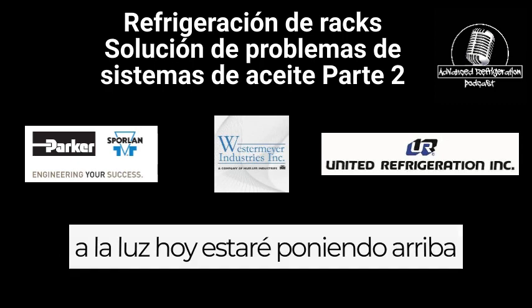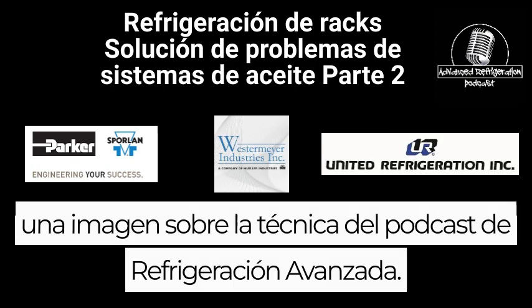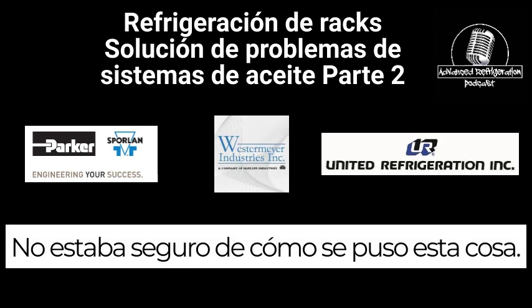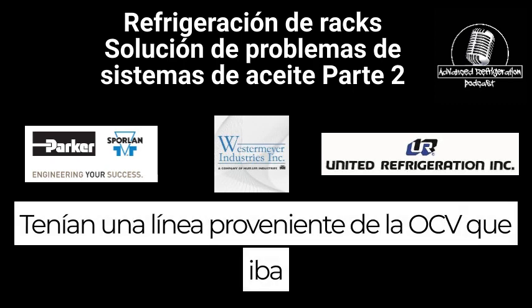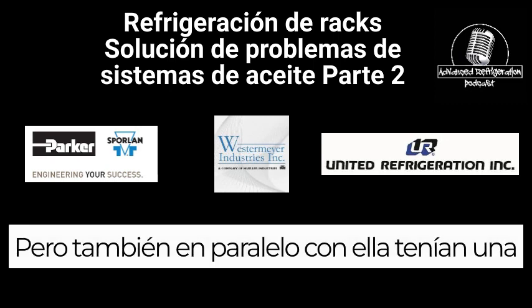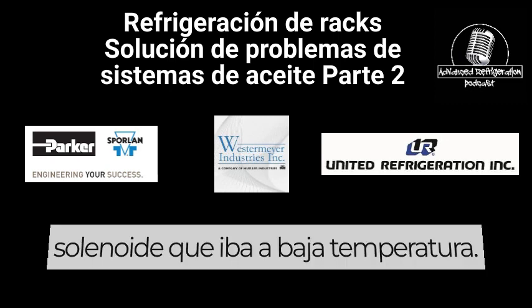Because it came to light today, I will be putting a picture on the Advanced Refrigeration Podcast Facebook. A technician sent me a picture. He wasn't sure how this thing was split. They had a line coming from the OCV going into the suction header for the medium tank, but also in parallel with it, they had a solenoid that was going to the low tank.